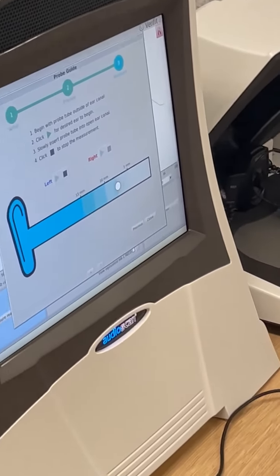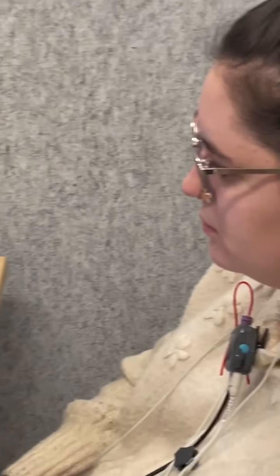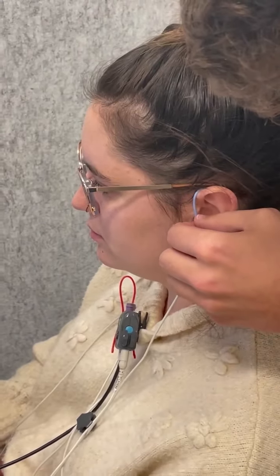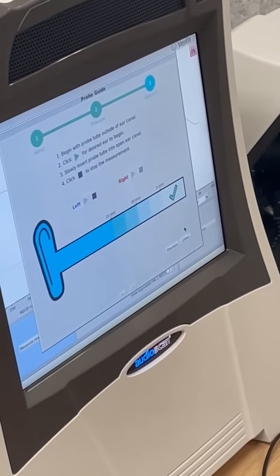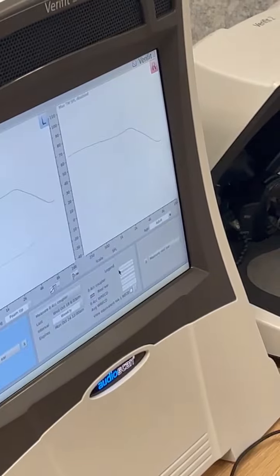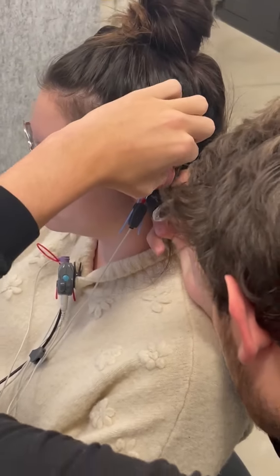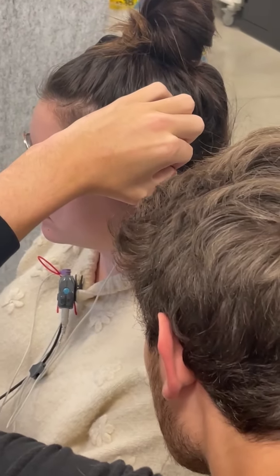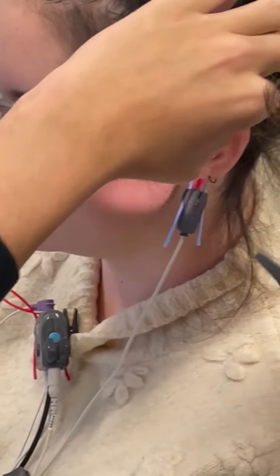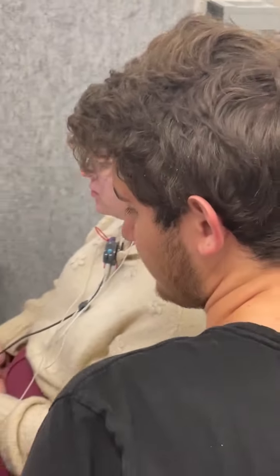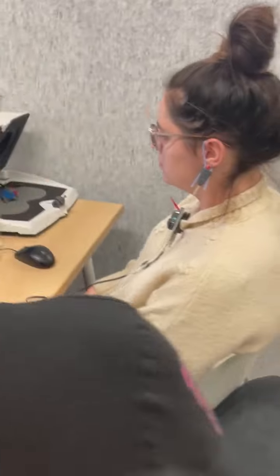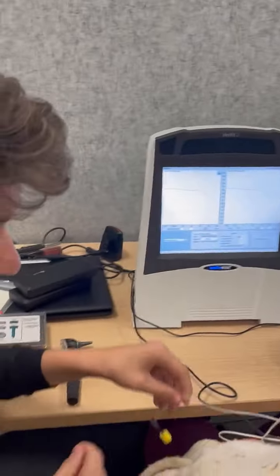After, we can use the probe guide to ensure that there was proper probe tube insertion, and we are looking for that green check mark which we see here. We can also make sure that the black ring on the probe tube is sitting at the intertragal notch, which will confirm. Once we're done, we do otoscopy once more to verify once again that it is in that anterior recess within that 5 millimeters from the eardrum.